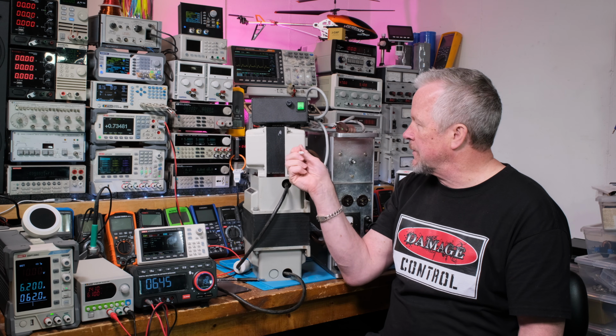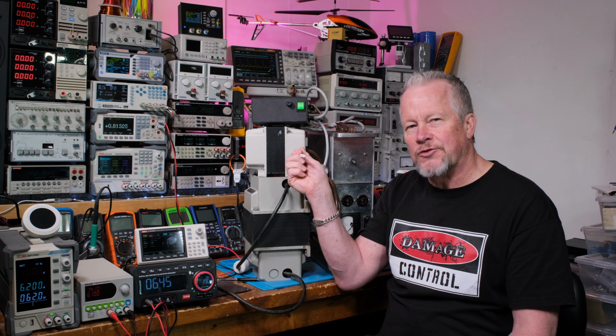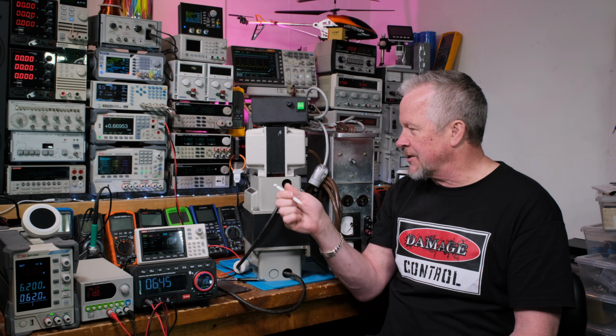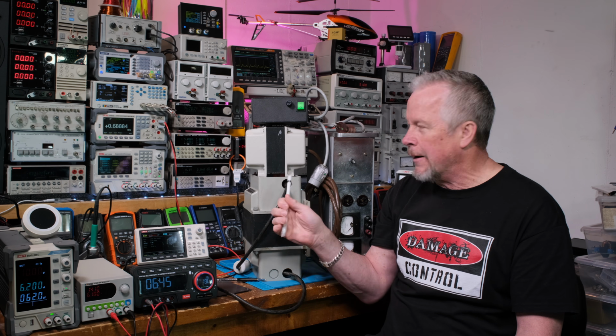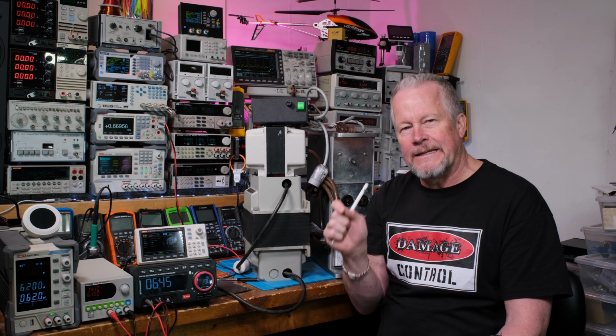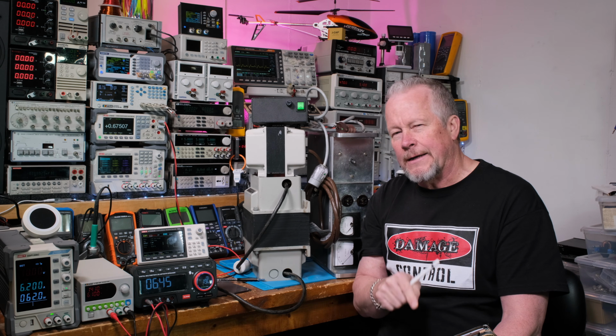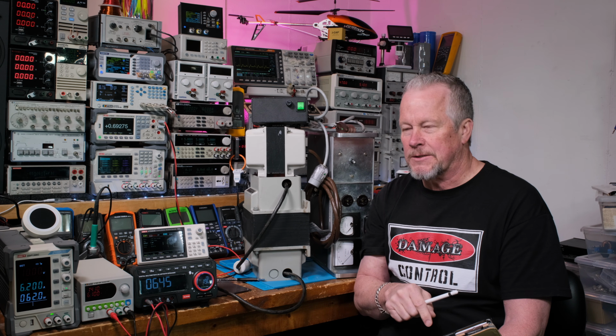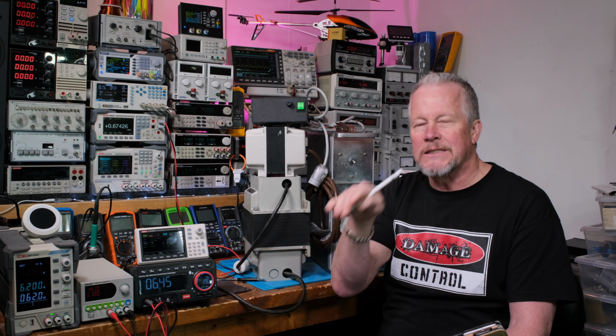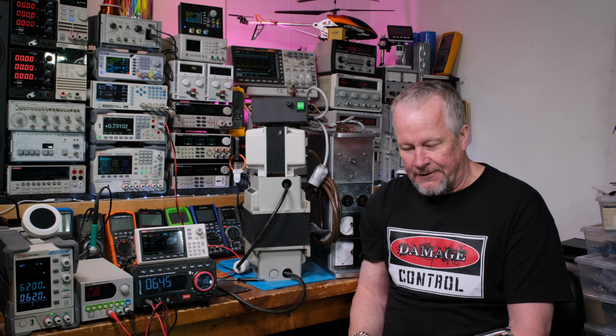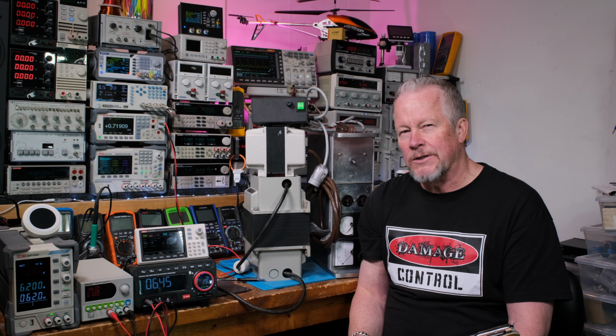That's why this one's called an extreme isolation transformer—very low capacitance. This one's an ultra, another name for it. They have very little capacitance. They purposefully try to minimize that capacitance as much as possible, so there's no leakage currents from the primary side into the secondary side. It also helps reduce noise.